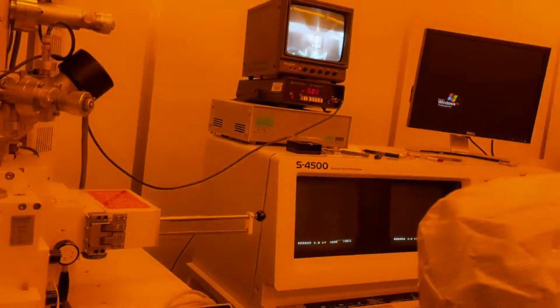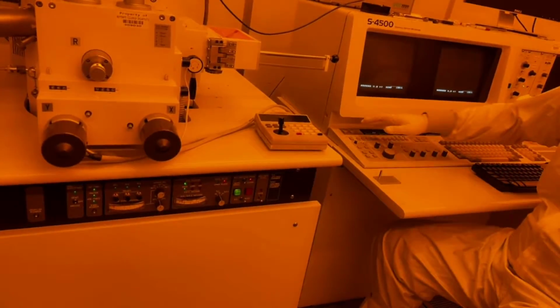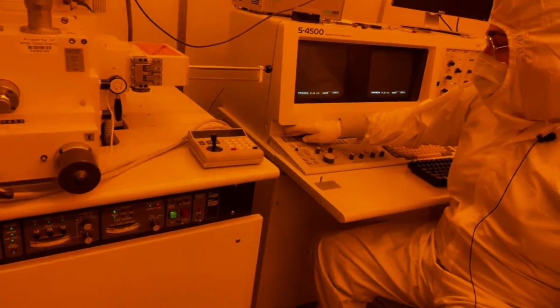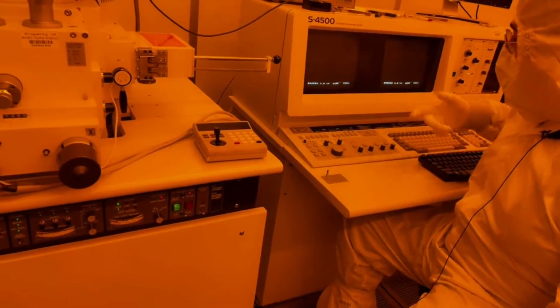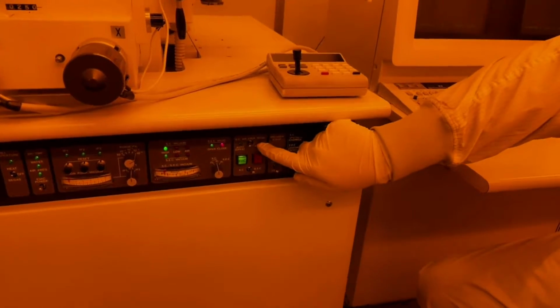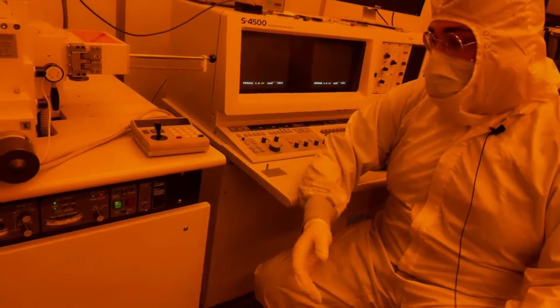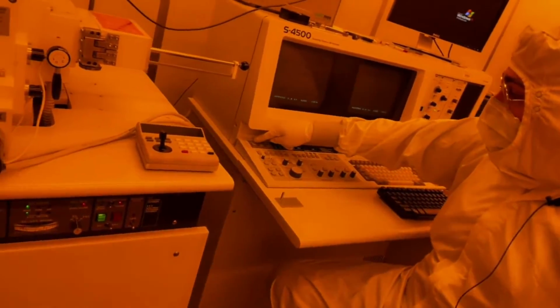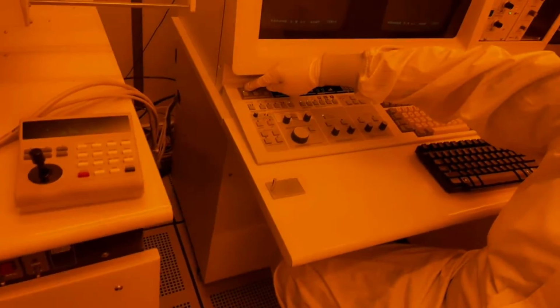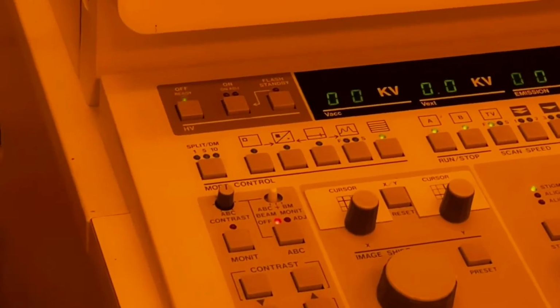Now the next thing is to open the sample chamber airlock. When you do that, you can see that this button here turns on. This indicator determines whether or not you can turn on the gun. So this is the airlock right here. The switch should be off when you're not using it, and then you open it when you're about to start using the gun. And when you open it, the indicator on the high voltage buttons will turn on. So you see this green light is on now, indicating that you can actually turn on the gun.